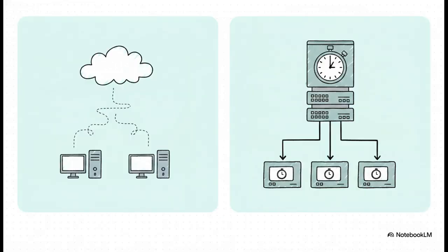To maintain that perfect synchronized chronological grid, you have to sync the time across all your devices. Now, you can use NTP mode, which relies on an external server. And hey, that's totally fine for basic PC networks. But for a highly integrated control system, SIMATIC mode is the absolute standard. In SIMATIC mode, the WinCC software sitting on the OS server acts as the ultimate internal time master. It actively pushes the exact time down to all automation systems via the plant bus, ensuring every single controller is ticking on the exact same millisecond.